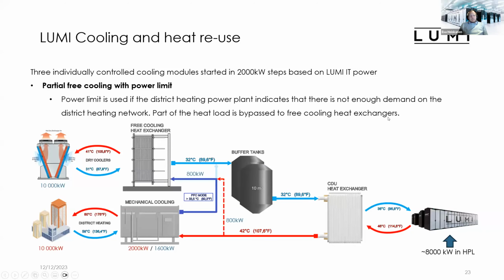Then we have this power limit with the partial free cooling, and this is used if the district heating power plant indicates that there is not enough demand on the district heating network. So we are not able to push all the excess heat from the Lumi to the district heating network, so we need to limit our district heating power. In this case, we are putting 800 kilowatts of power load to the free cooling heat exchanger, and 1.6 megawatts is cooled down with the heat pumps.